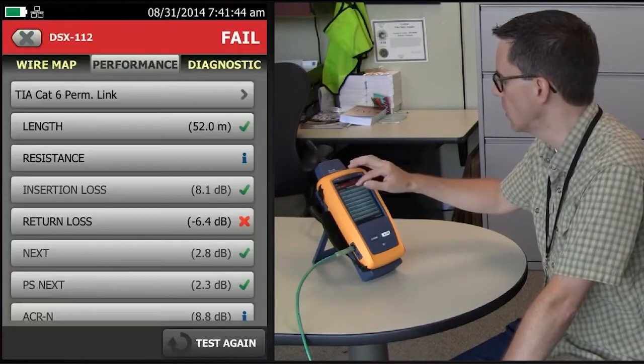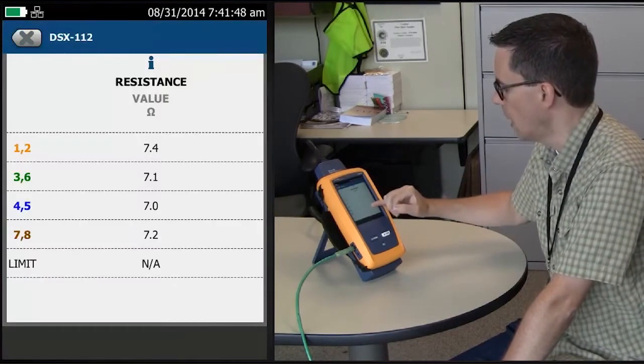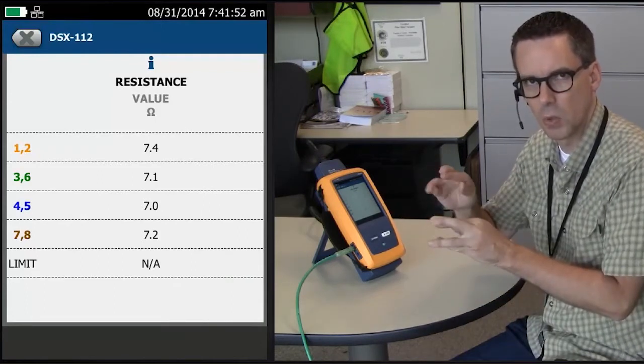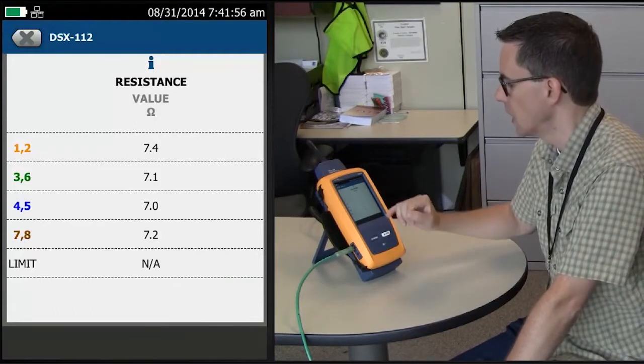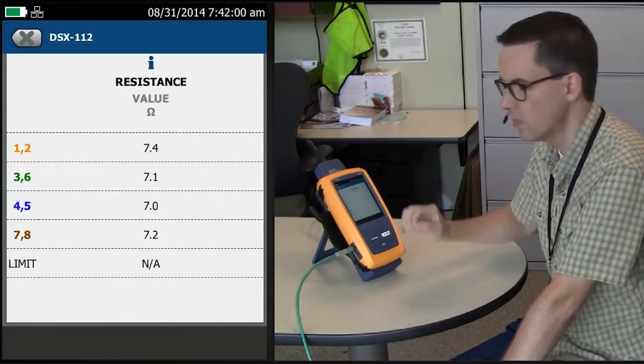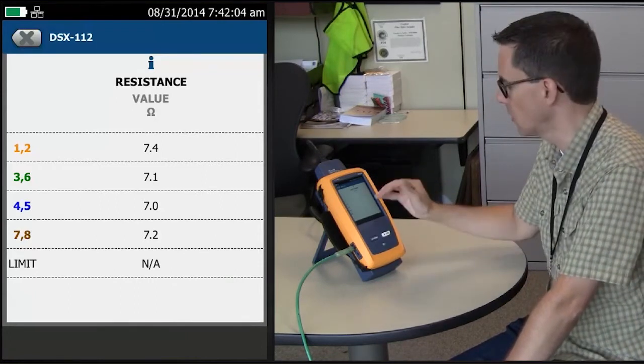So let's go and look at resistance. When we look at the resistance for four pairs, they are slightly different between each because that's the difference in the twist rates in the cable. But they're not significantly different. If they were more than an ohm and a half or two ohms difference between them, then I would be concerned about a DC contact resistance issue. That's not the case here.